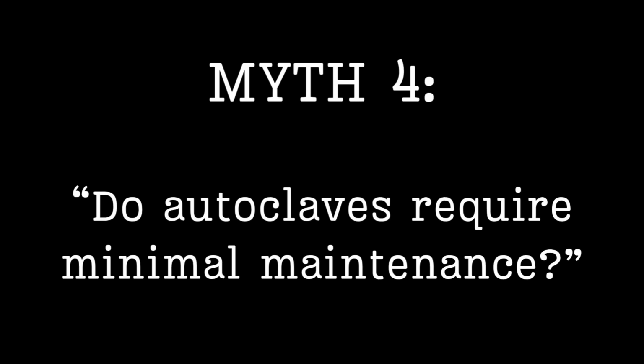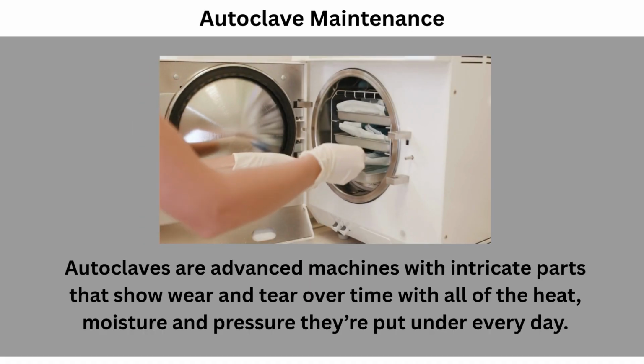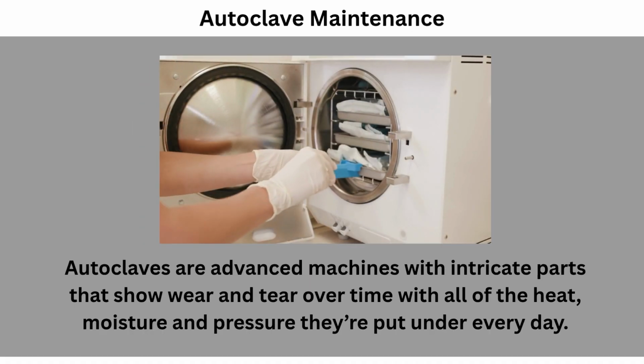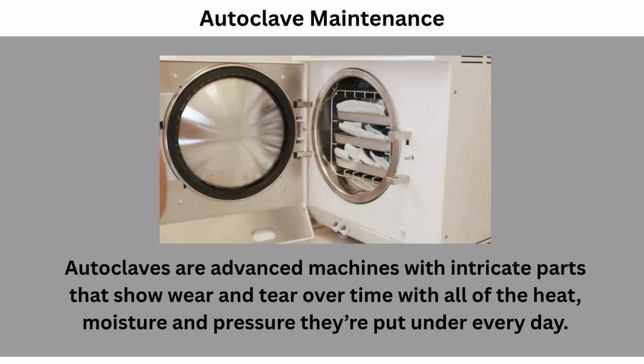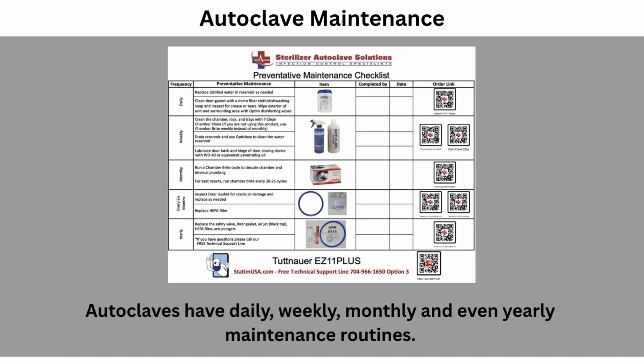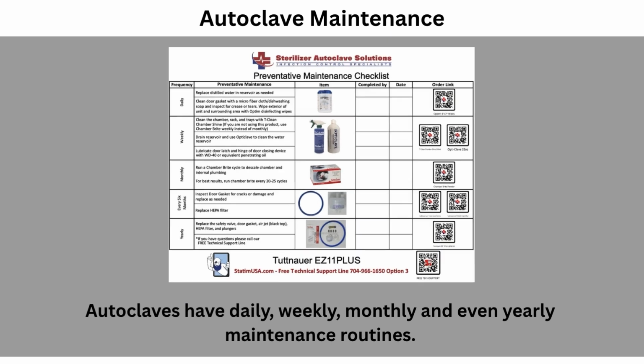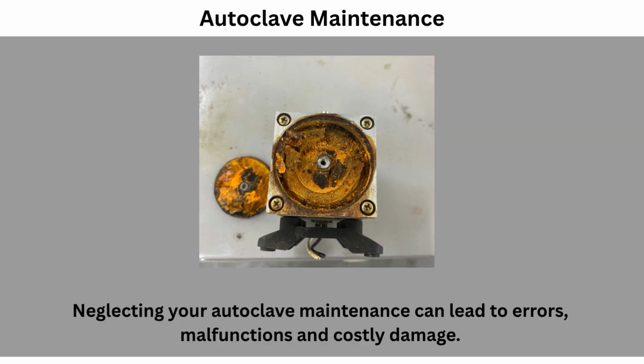Myth number 4. Do autoclaves require minimal maintenance? Autoclaves are advanced machines with intricate parts that show wear and tear over time with all of the heat, moisture, and pressure they're put under every day. Autoclaves have daily, weekly, monthly, and even yearly maintenance routines to ensure they're always in proper working order. Neglecting your autoclave maintenance can lead to errors, malfunctions, and costly damage.